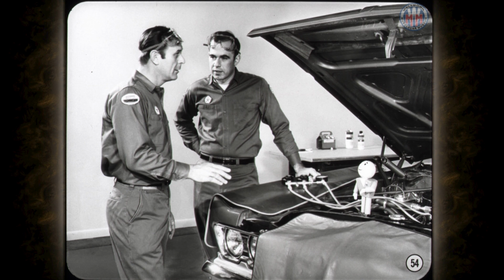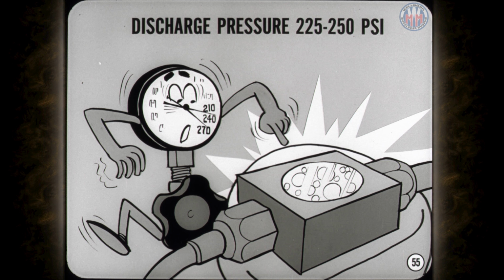To check the level, we run the engine at the specified speed and set the system controls as we did for the preliminary pressure check. In addition, we block the condenser airflow to raise refrigerant temperature and pressure. Blocking the condenser airflow should raise the discharge pressure somewhere between 225 and 250 for testing. If foam shows in the receiver dryer sight glass at this pressure, the refrigerant level is low and must be corrected before making the remaining pressure tests.